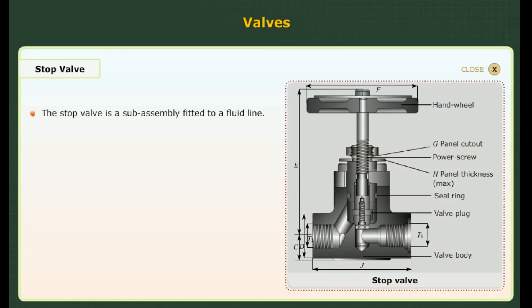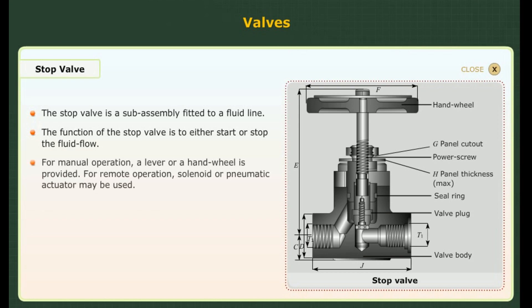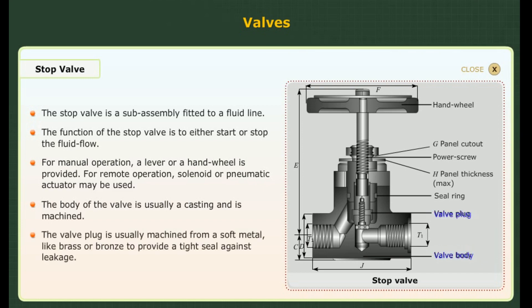Stop valve. The stop valve is a sub-assembly fitted to a fluid line. The function of the stop valve is to either start or stop the fluid flow. For manual operation, a lever or a hand wheel is provided. For remote operation, a solenoid or pneumatic actuator may be used. The body of the valve is usually a casting and is machined. The valve plug is usually machined from a soft metal like brass or bronze to provide a tight seal against leakage.